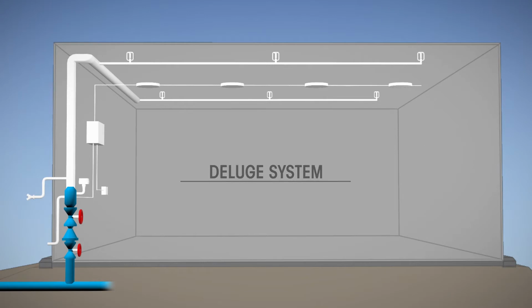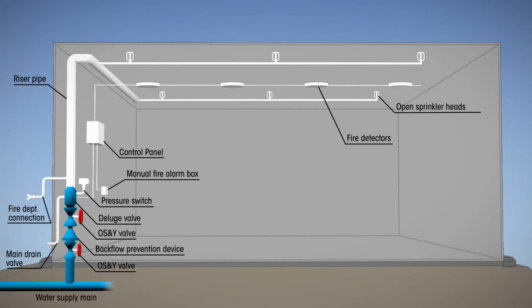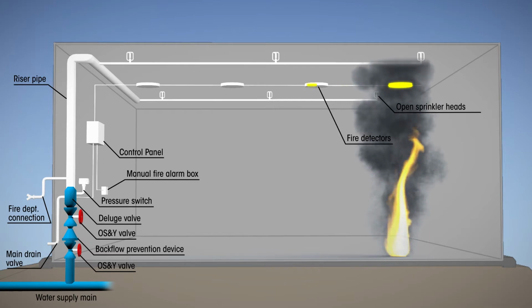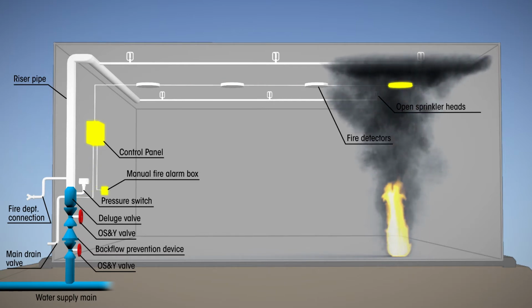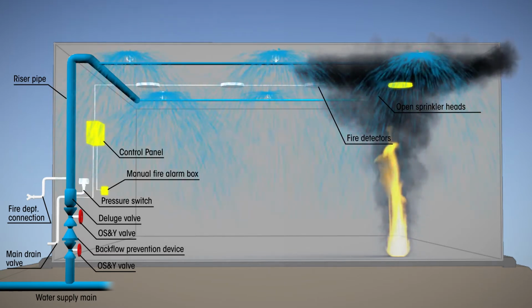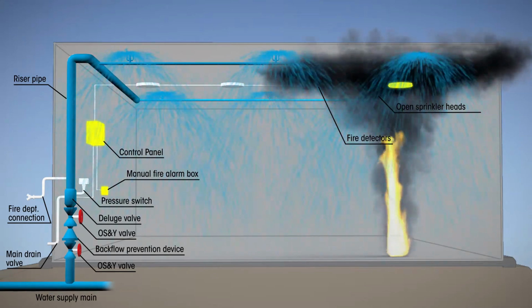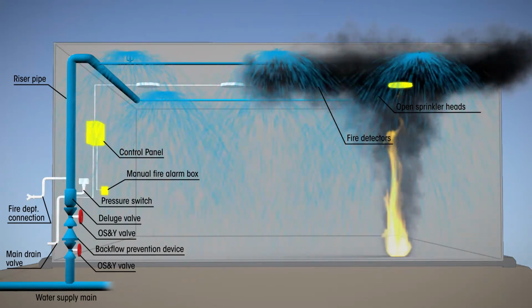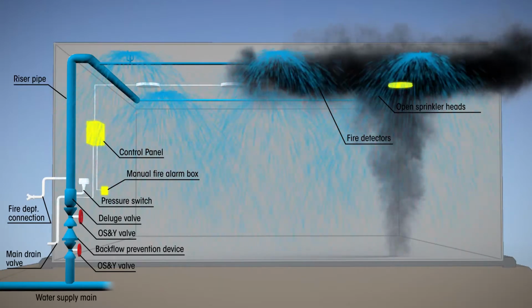Deluge sprinkler systems, which are intended for high-hazard areas, contain sprinklers or nozzles that are already open. They are part of a piping system that is connected to a water supply through a valve that is opened by the operation of a detection system installed in the same areas as the sprinklers or nozzles. When the detection system signals the deluge valve to open, water enters the piping system and flows from all sprinklers or nozzles at once.